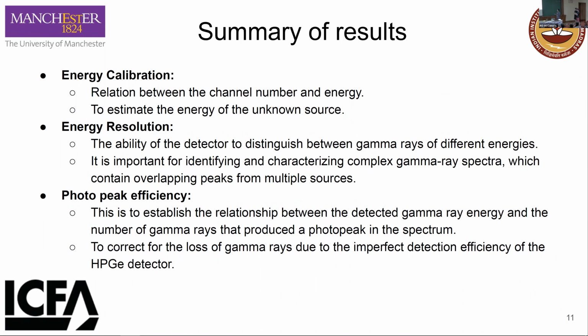And the last thing is the photo peak efficiency, which is the relationship between the detected gamma ray energy and the number of gamma rays that produce a photo peak in the spectrum. So photo peak efficiency is basically needed to correct the loss of gamma rays, the imperfect detection efficiency of the high purity germanium detector. So, coming to the last slide.